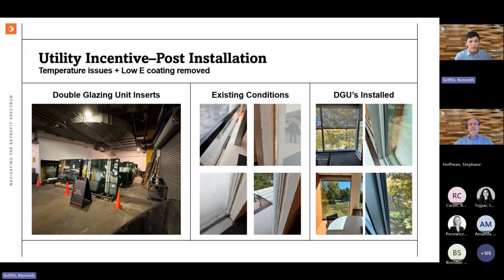But there were some things learned. One big thing was that the low-E coating had not been reapplied, so our solar heat gain coefficient wasn't what it was supposed to be. It was supposed to be about 0.31, but it was somewhere closer to 0.55, causing temperature issues. So the low-E coating then had to go on and be reapplied.